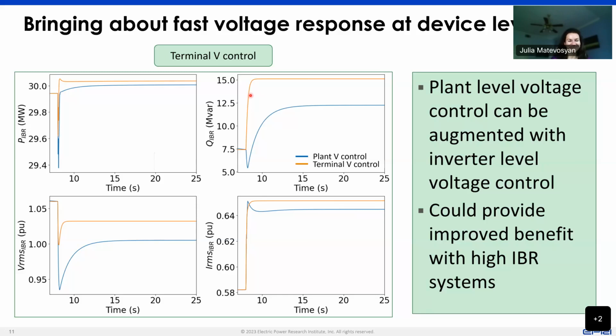So my personal opinion here is that an inverter-based resource itself has tremendous capability that can be leveraged. And if we ask them to mimic a synchronous machine, although the advantage of doing that is in some ways a characteristic of performance that an operator might be used to, so they might know how to react if a certain disturbance occurs, the flexibility that we might leave on the table because we're not utilizing the full capability of the inverter-based resource might have an impact on the system.